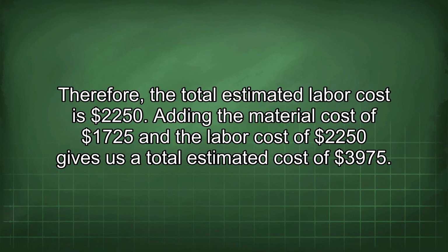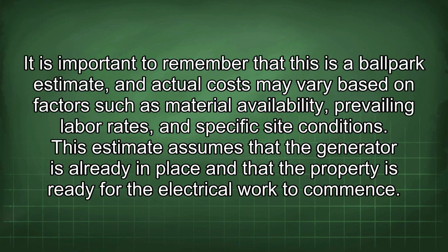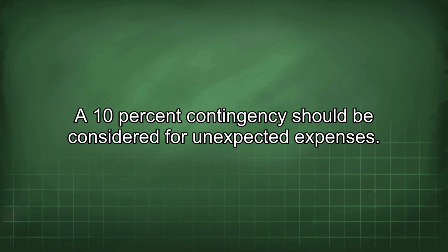Adding the material cost of $1,725 and the labor cost of $2,250 gives us a total estimated cost of $3,975. It is important to remember that this is a ballpark estimate, and actual costs may vary based on factors such as material availability, prevailing labor rates, and specific site conditions. This estimate assumes that the generator is already in place and that the property is ready for the electrical work to commence. A 10% contingency should be considered for unexpected expenses.